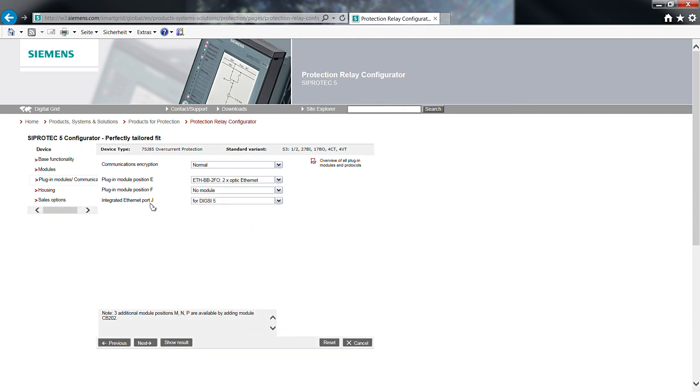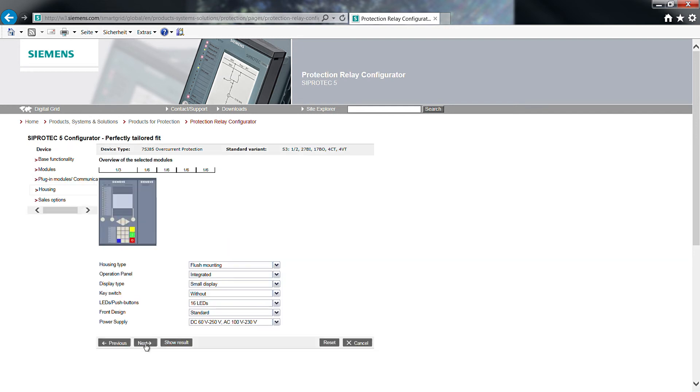An optical Ethernet module ETH BB2FO 2 times optical Ethernet will be placed in plug-in module position E. Plug-in module position F is not used for our application. The integrated Ethernet port J is used as the interface to an engineering PC.